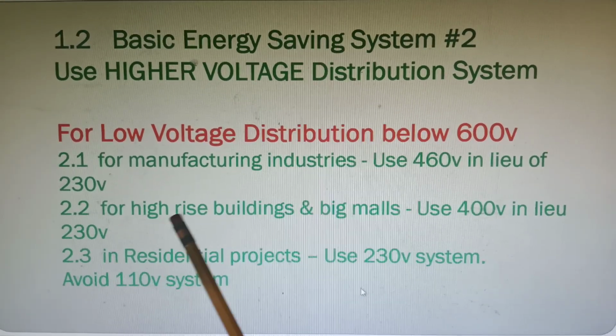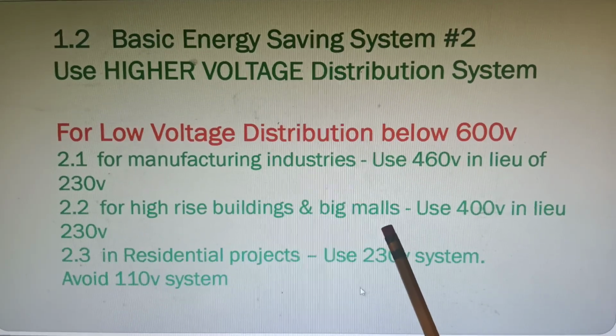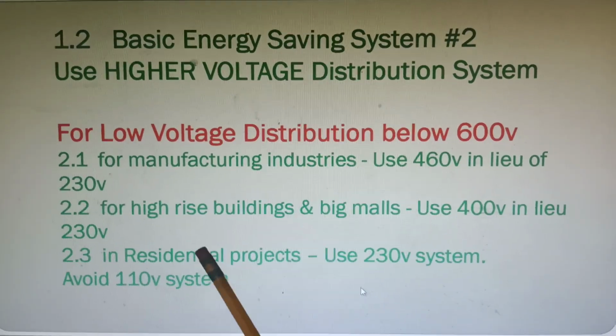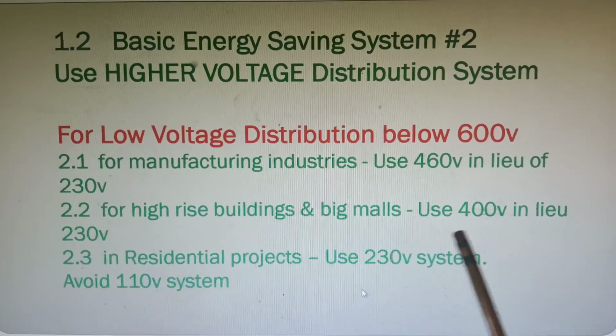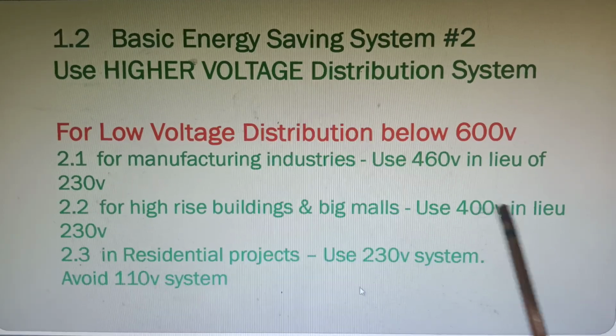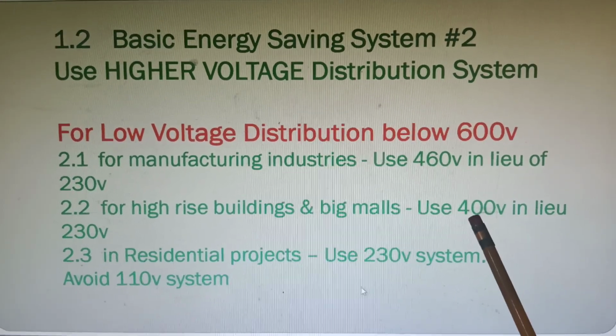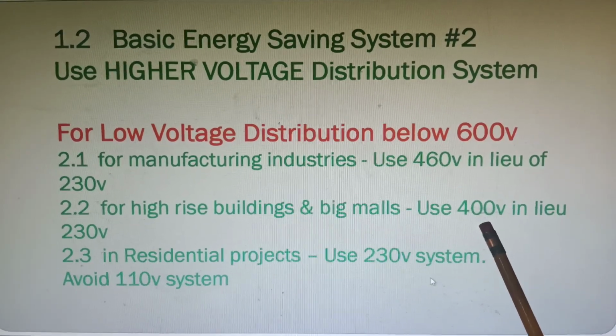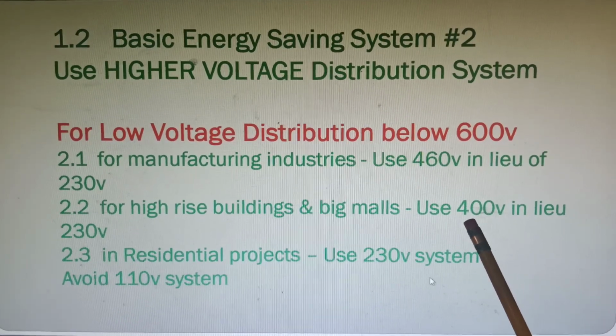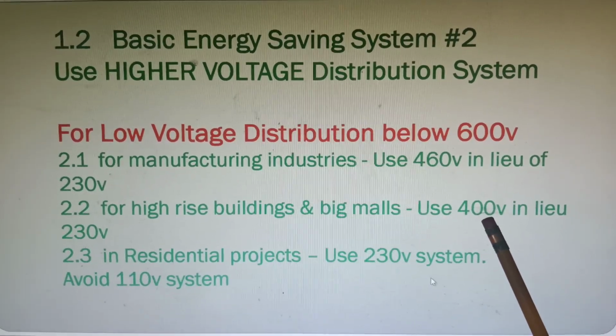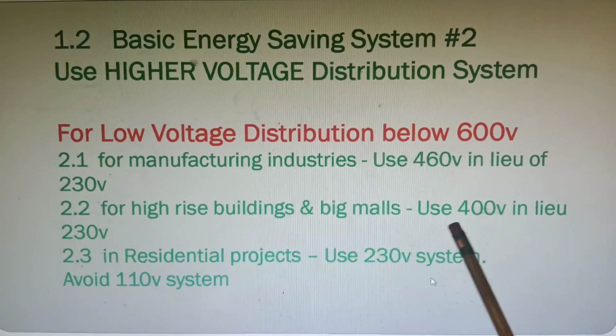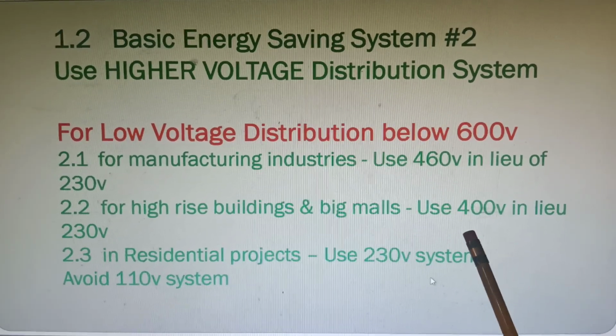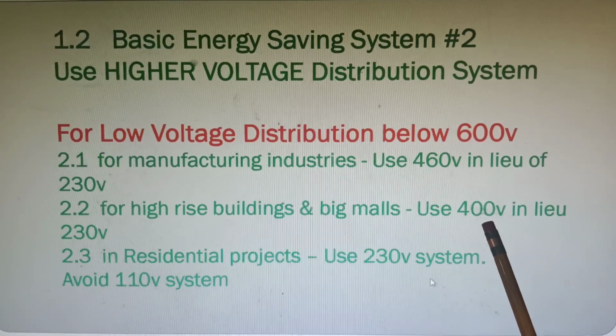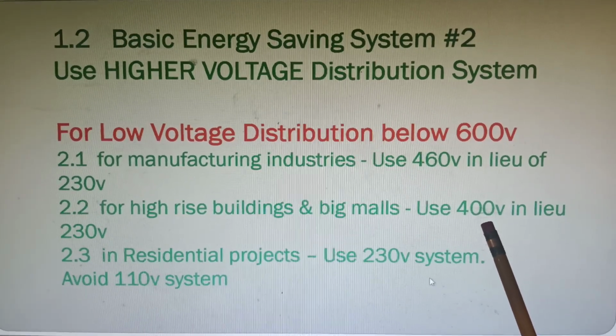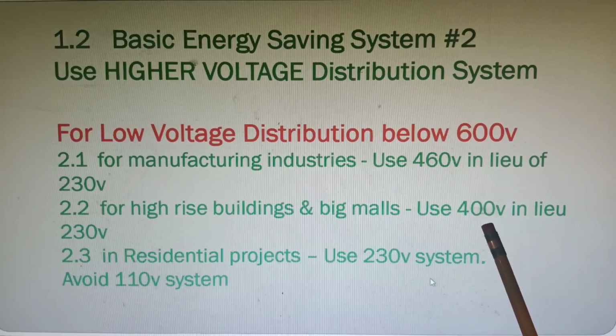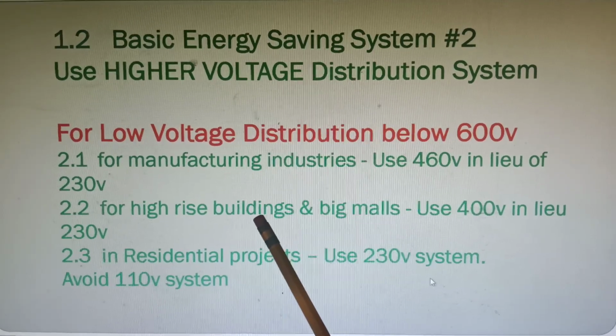But in the case of a high-rise building and malls, the usual system is much better with the 400 volt system, because in the 400 it's a 3-phase 4-wire system, and the line to neutral of this system is 230 volts. So that means therefore that there will be no need for a step down transformer to bring down the voltage for the lighting loads and the small power loads.